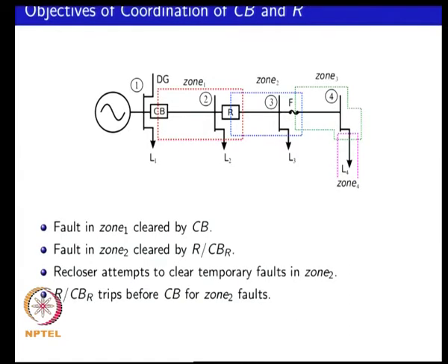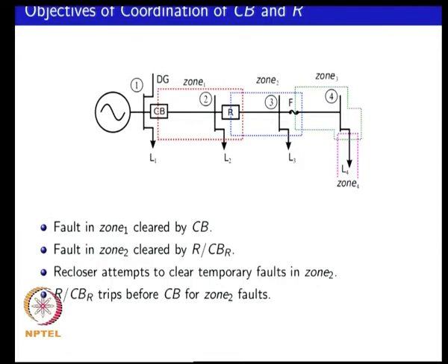We will call zone 1 the zone of protection for the circuit breaker and zone 2 corresponding to the recloser. If you have a fault in zone 1, it is the circuit breaker that has to protect. If you have a fault in zone 2, the recloser with its underlying circuit breaker characteristics should provide protection. If you are having temporary faults in zone 2, the recloser attempts should clear them.